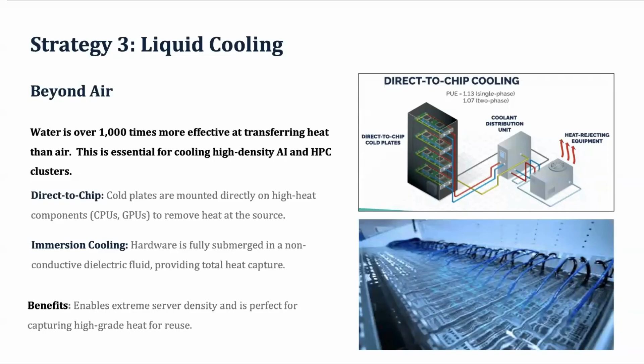The second one is immersion cooling. As seen in the picture, the entire server is dipped in the liquid, and that liquid will absorb all the heat being generated. The benefit of this is that it suits very high server density, and these two methods are very much recommended. But this has some challenges as well, because if a server gets any problem, then the entire unit needs to be switched off to get that server out and all those things. But in direct to chip cooling, that problem does not arise, so that can be easily used.